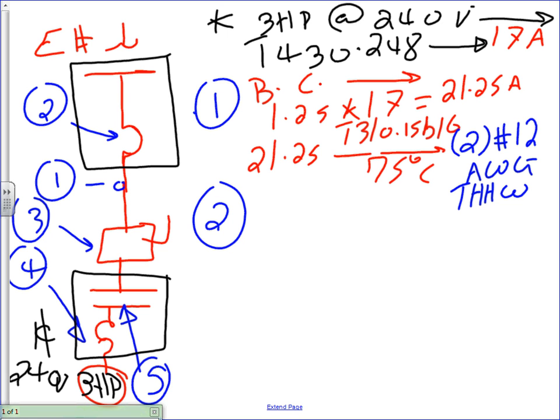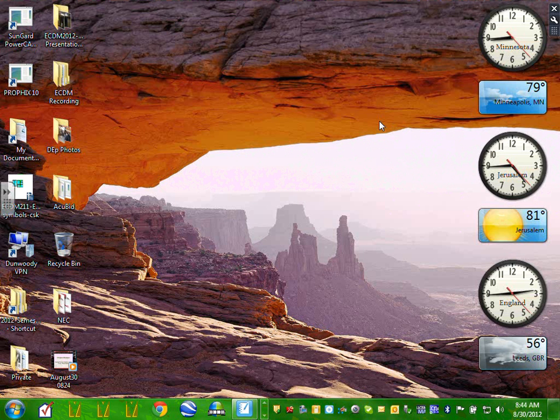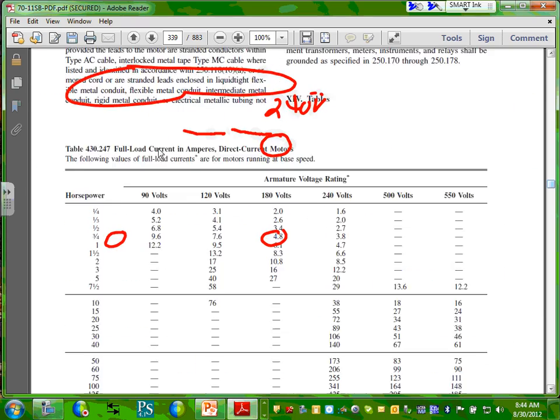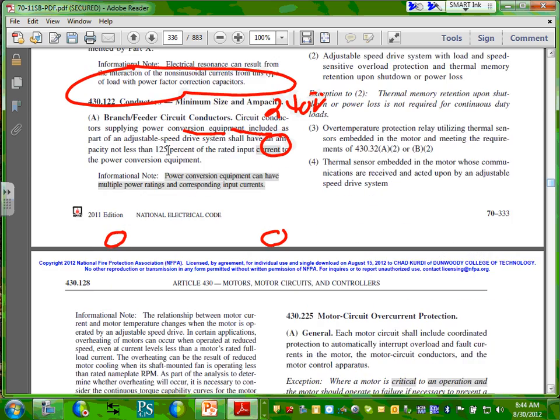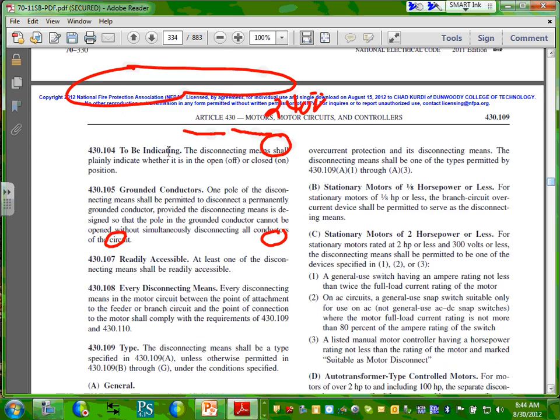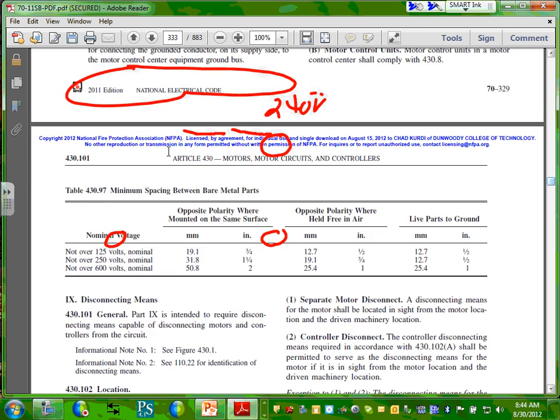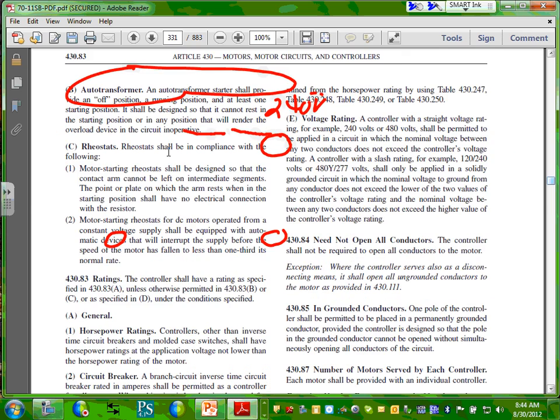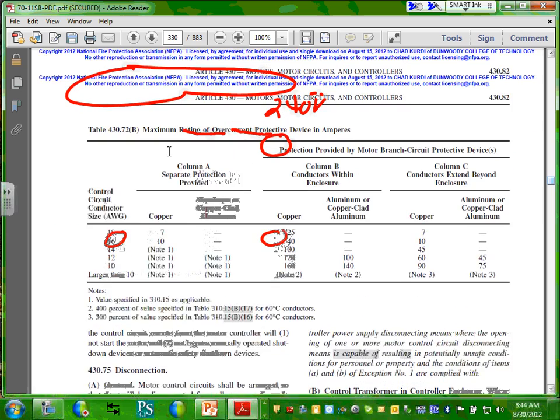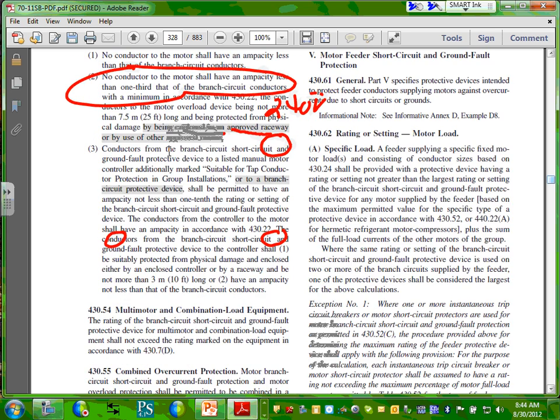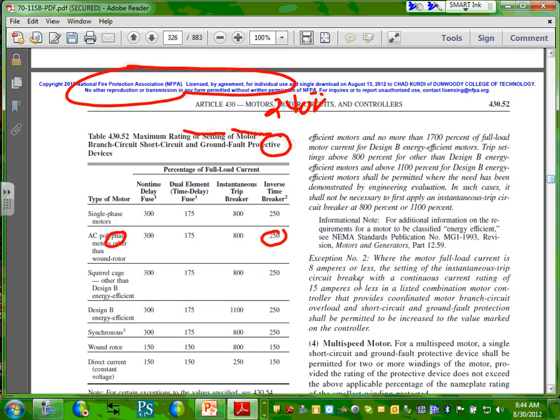Number 2. I need an overcurrent protection device, and it's a circuit breaker. Here's what the code says. Let me minimize here and go directly to my code. Let's go to a very important table, if you haven't highlighted this table, 430.52. Where am I here? Okay, all right, here you go. So let's go to this table.